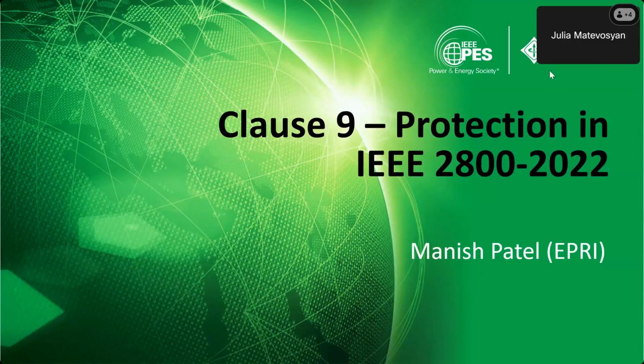All right, so this is a little difficult topic to prepare a presentation for, because the protection requirements in the standard are pretty brief. I could just, in simple words, say that the standard requires that any protection applied within the plant shall not interfere with the plant's ability to ride through the voltage and frequency disturbances as specified in the standard, full stop, and we are done with protection requirements. But we did add a little more details in the standard. But again, I think when you read about 2 pages worth of content in clause 9, you can walk away with the conclusion that I just mentioned. So let me try to elaborate a little bit more on this.